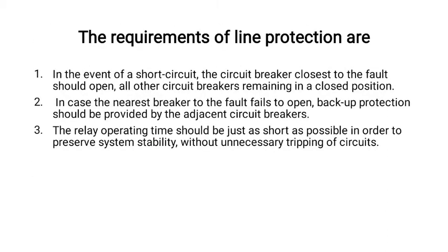Now, what are the requirements of line protection? In the event of a short circuit, the circuit breaker closest to the fault should open, with all other circuit breakers remaining in a closed position. In case the nearest breaker to the fault fails to open, the backup protection should be provided by the adjacent circuit breakers. The last one: the relay operating time should be as short as possible in order to preserve the system stability without unnecessary tripping of the circuits.